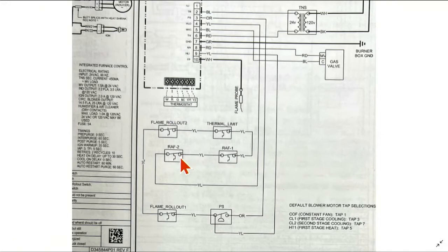Normally closed in this case. This symbol means temperature. And notice that if the switch goes up, it will open. That means this will open on temperature rise. If this switch was on the bottom side in the same orientation, it would mean open on temperature fall.